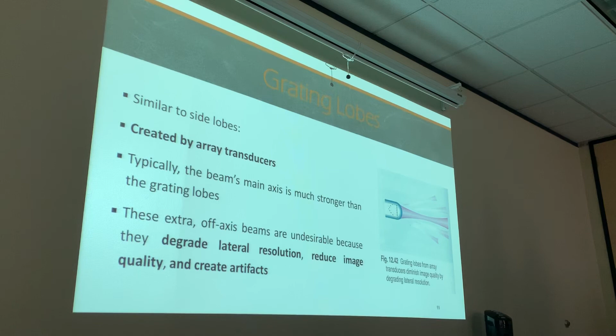So, again, exactly what I want you to know about this. Side lobes, single element transducers. Degrade lateral resolution. Create artifacts. Reduce image quality. Grating lobes, array transducers, same thing, they're very similar. They also degrade lateral resolution, reduce image quality, and create artifacts. They create noise on our image.